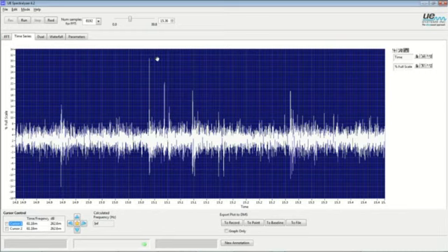With other types of events, such as corona, you would see, even on nuisance corona, a predictable pattern where the ionization of the air takes place. The timing in between each one of these spikes on the time domain would be linear and uniform. That is absolutely not what we have, particularly right here, just to pick a slice. And I'll zoom in on that just a little bit more using the magnifying tool, and we should be able to see that a little better here.